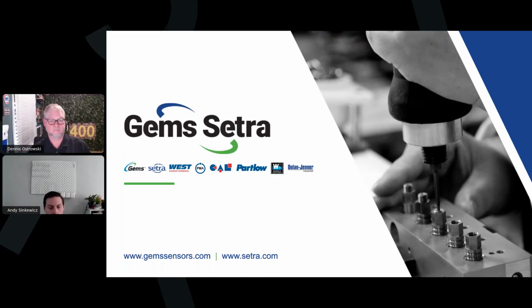Great. Do you have a min or max velocity rating for the meter? Do not. Just flow rates is the only min-max that's listed here. I don't think that the acoustic velocity for any liquid exceeds what's possible for this device. You could have thick molasses running through it, as well as super light water-based liquids, right? That the sound's going to travel much faster through. So really, the media type is independent from the flow rate that we can measure with this device.